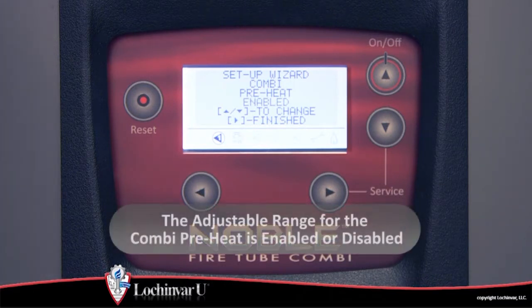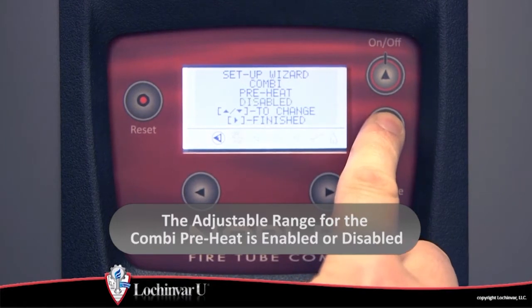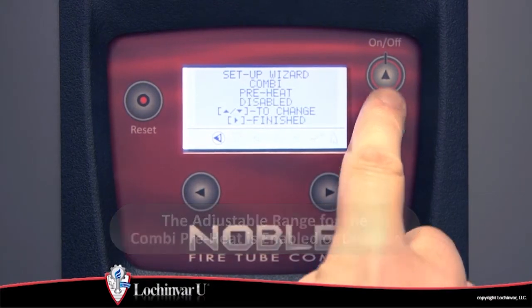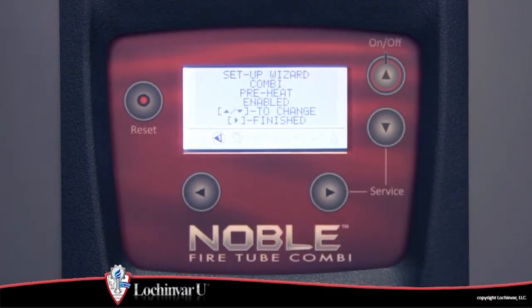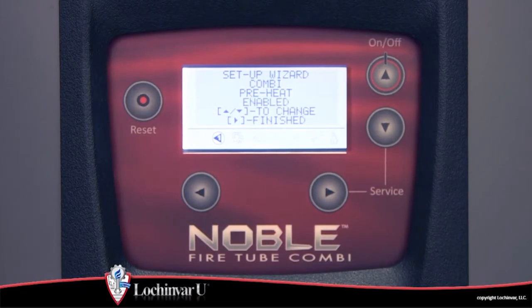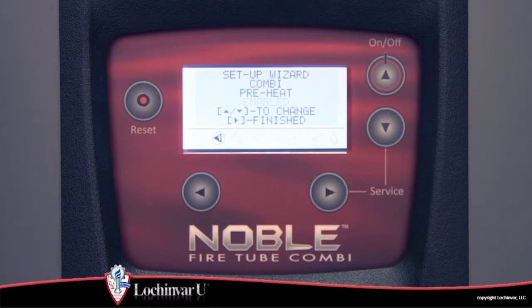The adjustable range for this parameter is enabled or disabled. Enabling this feature can increase fuel usage as the unit will periodically fire to maintain the heated water in the boiler, keeping the secondary heat exchanger hot for immediate use.